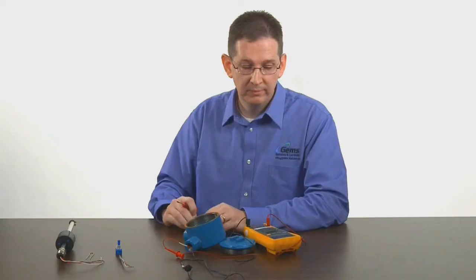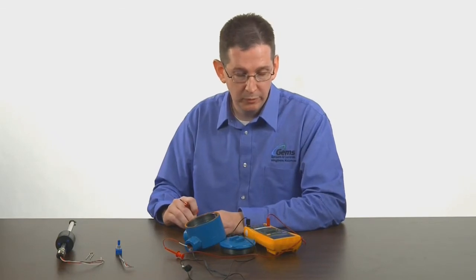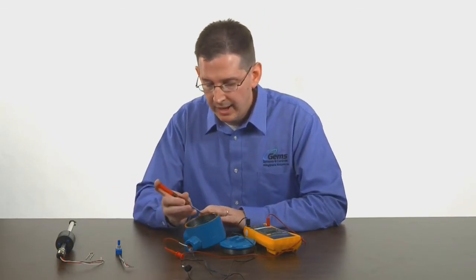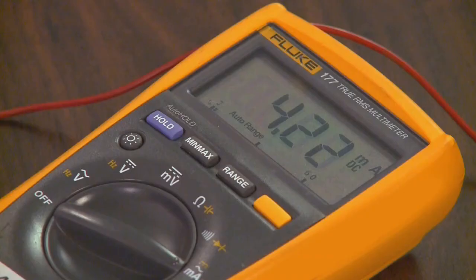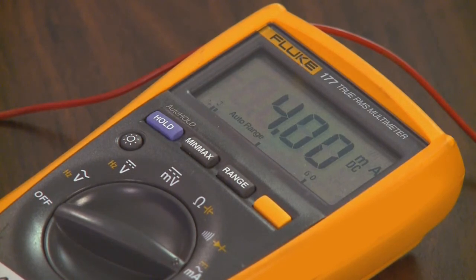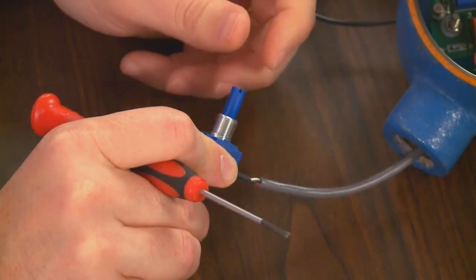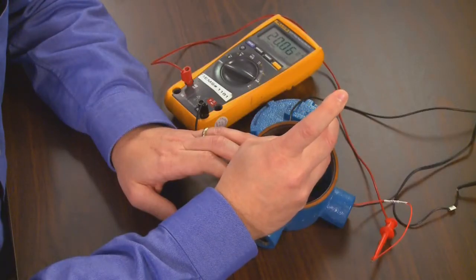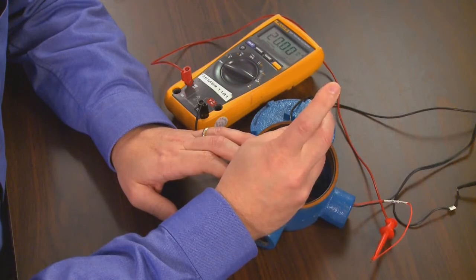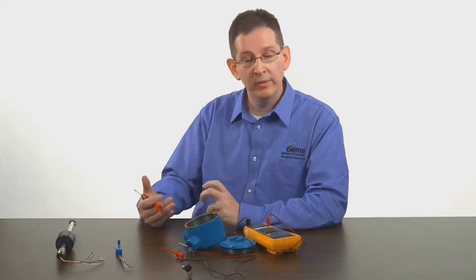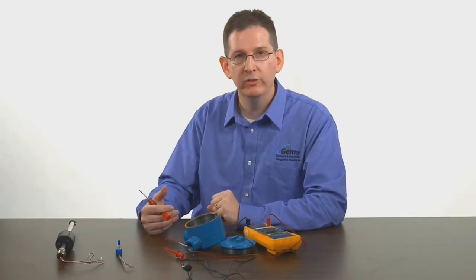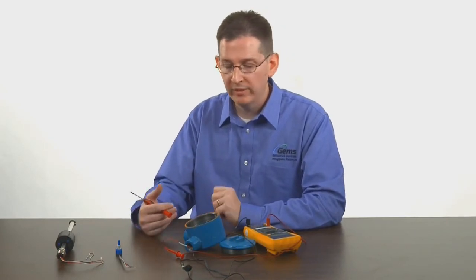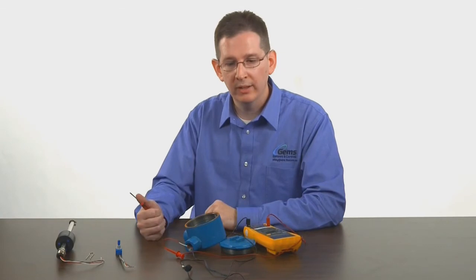Once that's done, we take the potentiometer fully counterclockwise and do the null potentiometer. Now these do affect each other, so what we want to do is this two or three times total. If we bring the potentiometer fully clockwise, you'll notice that the output has actually changed and we tweak that back towards the 20 milliamp point. As I said, doing that two or three times will pull that into your 4 and 20 points. Once you're done, your unit is fully calibrated.